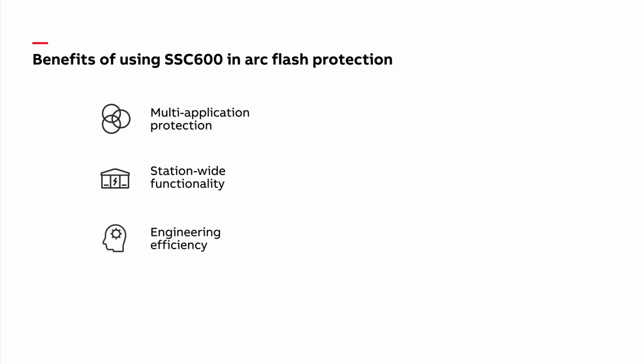Engineering efficiency. As the complete protection application is centralized, building arc flash protection with selectivity is fast and easy. Also, maintaining the protection application is straightforward. Safe switching operations. Local control and enabling protection are done via web HMI, thus decreasing the need for operative personnel to be in close proximity of energized switchgear. For increased safety when working near switchgear, the web HMI can be used to switch off current condition. This will allow faster reaction speed of the arc flash protection.